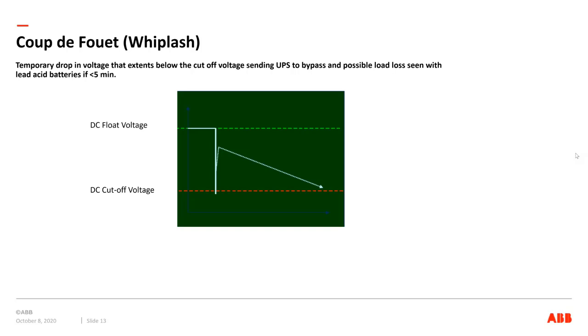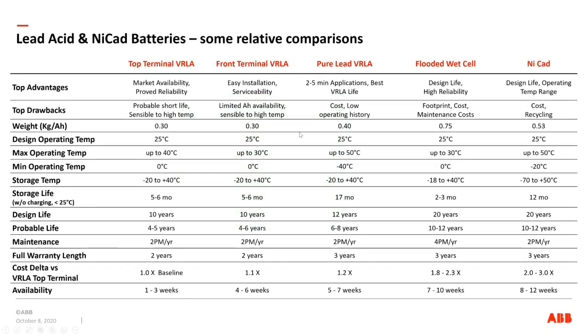And then onto the next slide, 14, which is, Jürgen, does the pure lead battery fail open or does it fail closed? Same failure mode as a VLA battery, it fails open. Okay, great. Typically, it fails open. It's not 100%. There's no guarantee that a wet cell will fail shorted, but they practically always do, and the VLAs practically always fail open. So the VRLA is a VLA battery. It's the same failure mode.